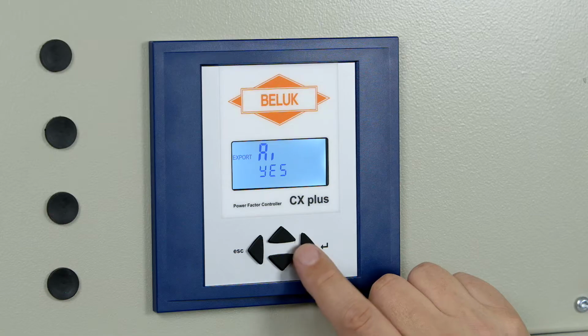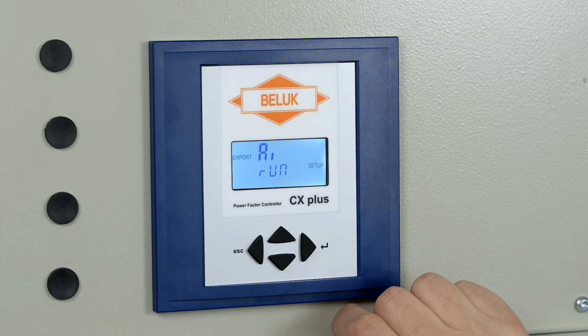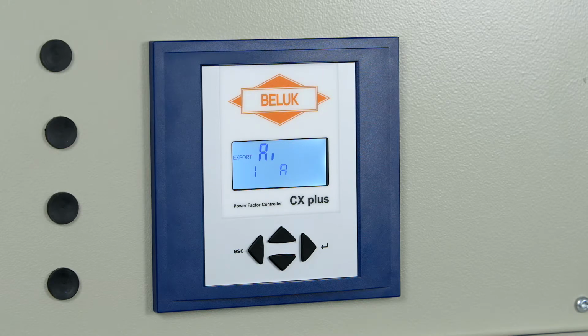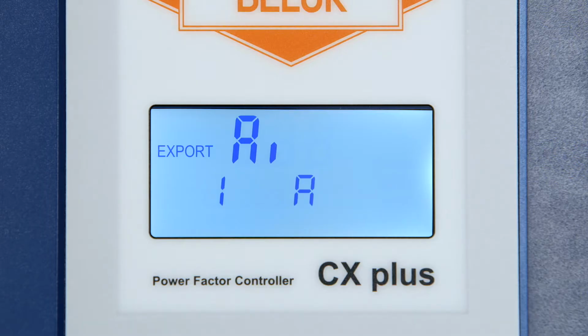This is followed by an option if the controller should run an automatic query of all switching outputs or whether this should happen manually. This process is called automatic initialization, AI for short. The Power Factor controller now switches all outputs on and off successively in several passes. The progress is shown in the display. The phase offset angle between current and voltage is determined automatically during this process.